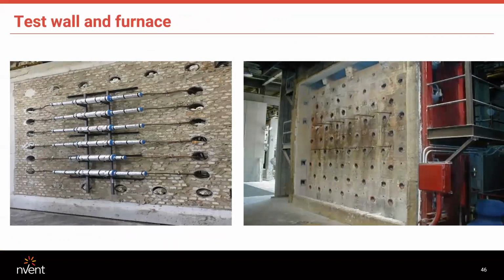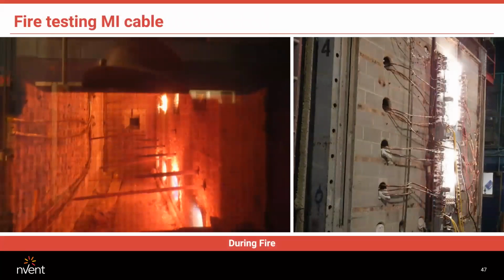And here you can see a picture of some cable going in for a UL test. While the cable is in there for the UL test, you can see on the right that some light bulbs are being powered. If any of those light bulbs go out during the test or fail to come on after the hose stream test, your cable has failed the test.